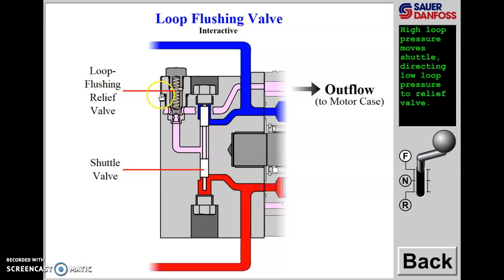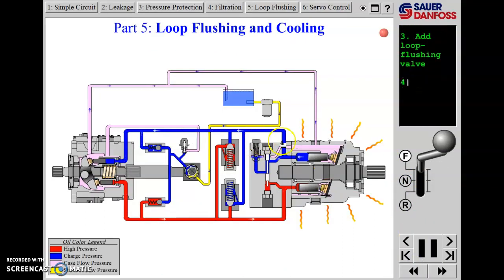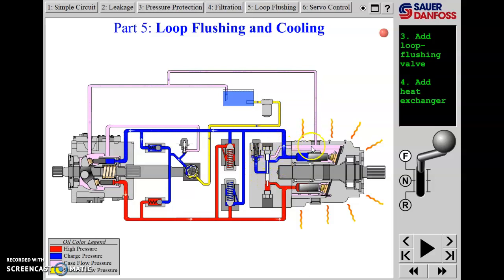The primary function of the flushing relief is not to control charge pressure — it is to ensure that some return flow from the motor crosses the shuttle valve and flows through the flushing relief. That adds flow to the case drain of the motor. By adding case drain flow to the motor through this path, we're dumping extra oil into the case that helps take heat out of the motor, and then it flushes back toward the reservoir.